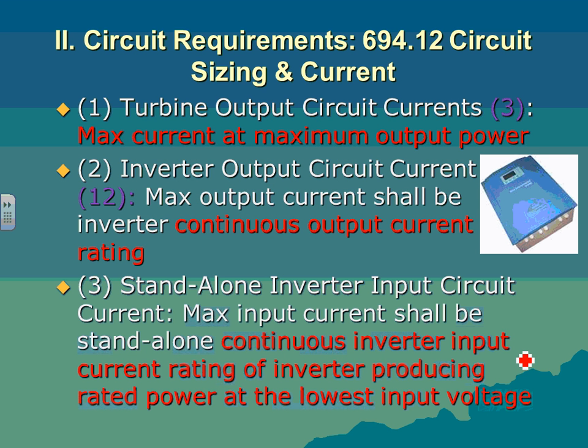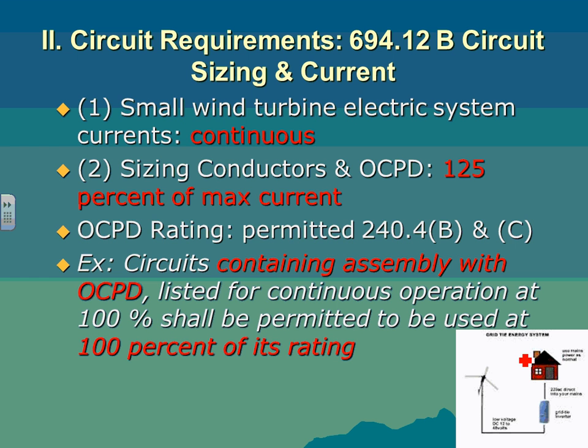So when you size your conductor, if you remember, 1.25 times the Imax, that's where the Imax is defined for all these systems. Small wind, they tell you very clearly, it's continuous load. We're familiar as electricians, guys, what do you do with a continuous load? 1.25 to size conductors, and for the most part, 1.25 to size overcurrent devices, with some exceptions for motors and HVAC equipment. These are straightforward sizing, 1.25, like we said, for these circuits.